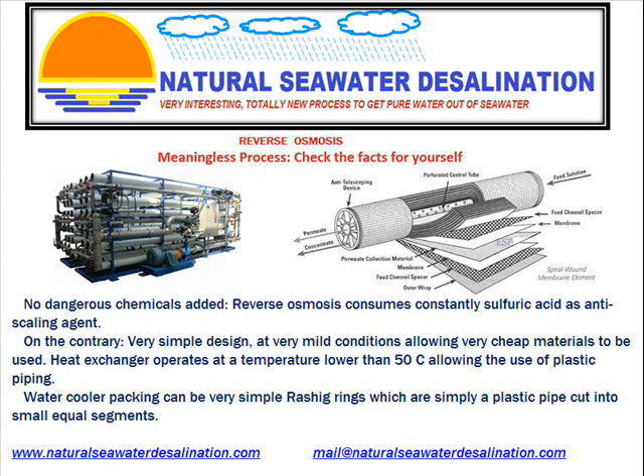No dangerous chemicals added. Reverse osmosis consumes constantly sulfuric acid as an anti-scaling agent. On the contrary, our process has a very simple design at very mild conditions, allowing very cheap materials to be used. The heat exchanger operates at a temperature lower than 50 centigrade, allowing the use of plastic piping. The water cooler packing can be very simple Rashig rings, which are simply plastic pipe cut into small equal segments.